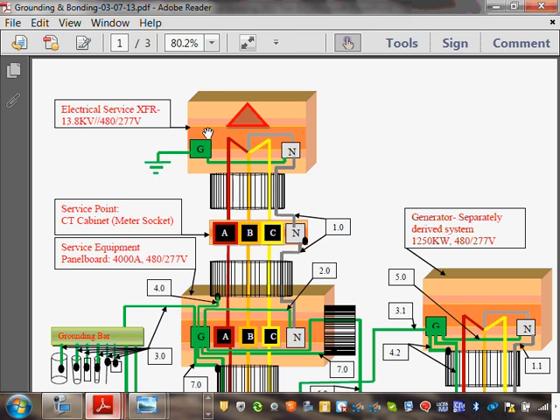You don't have a neutral for impedance grounded. We don't pull a neutral. So the neutral will disappear if your system is impedance grounded or ungrounded. Everything else stays the same.